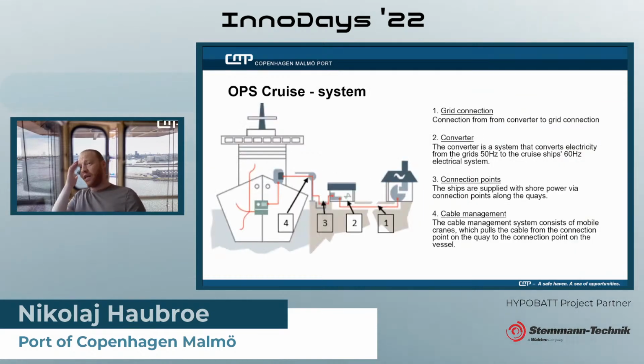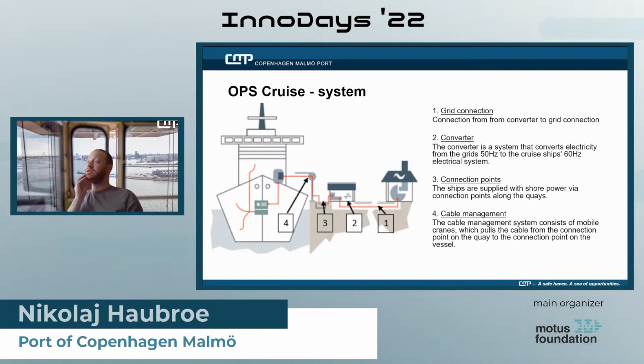We have identified 4 major parts of the system. In order to build this, we've looked at the grid connection, the converter, which we need to convert from the European grid's 50 hertz to the cruise ships' 60 hertz electrical system, the connection points on the quays, and the cable management system that brings power from shore to the cruise ships.